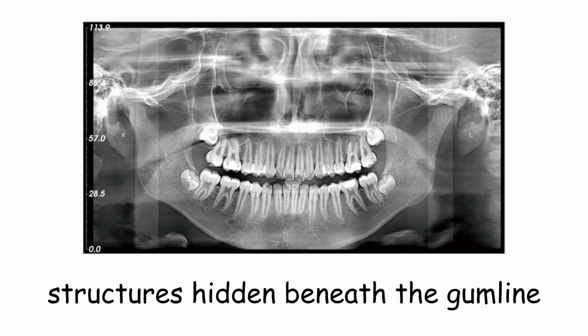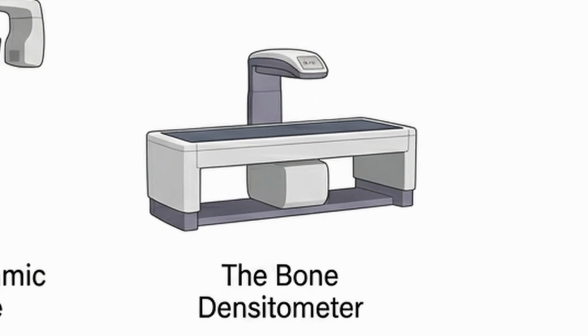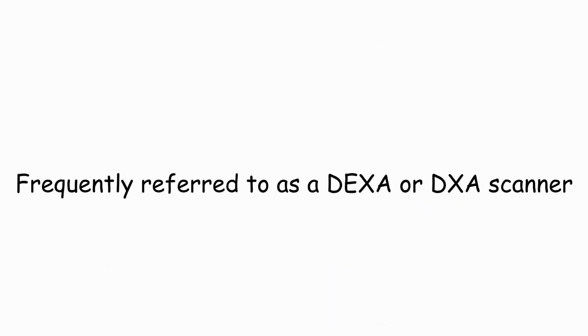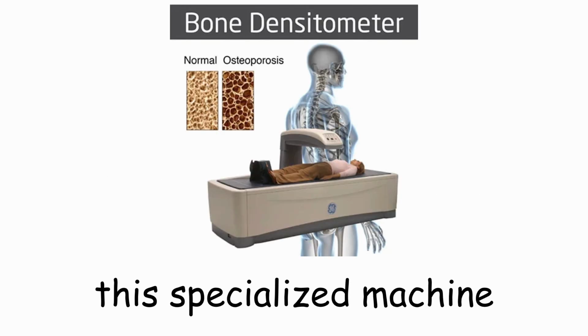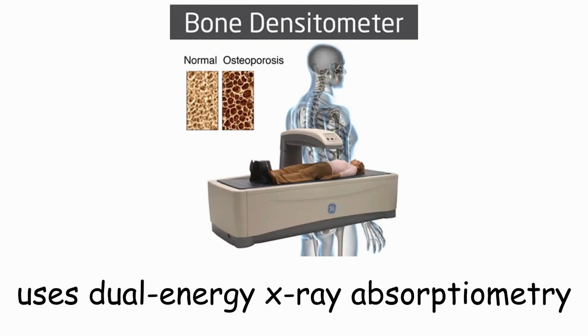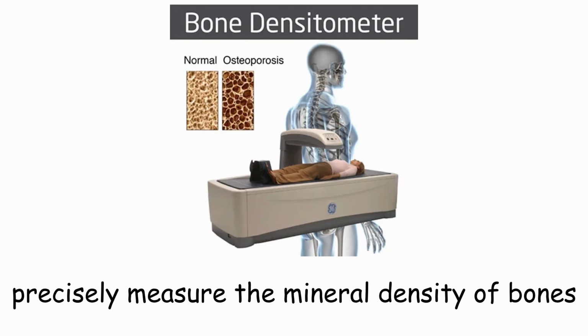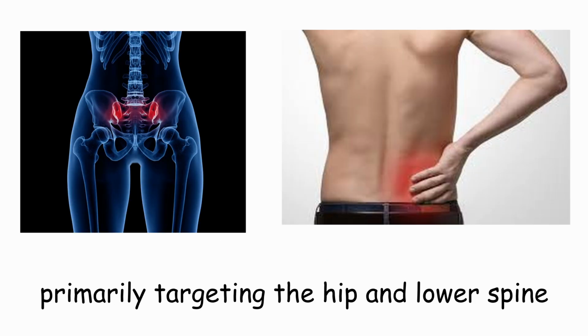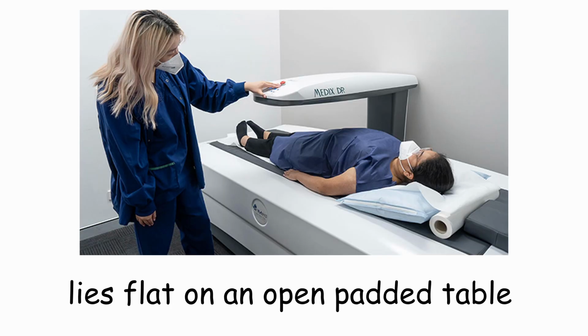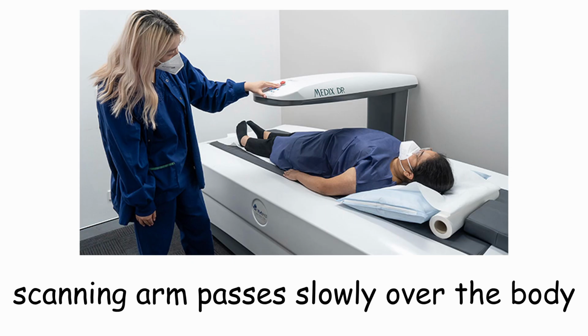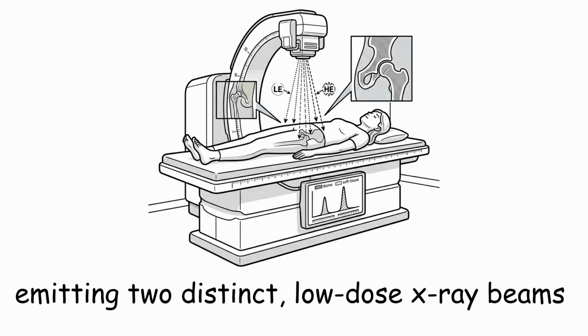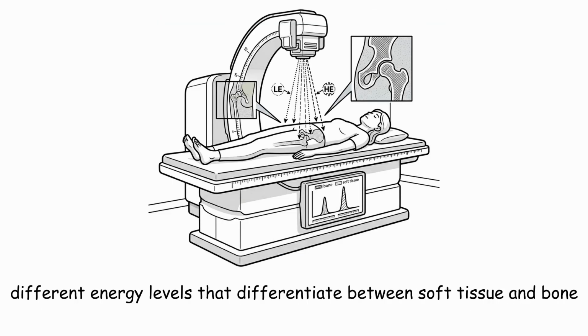The bone densitometer. Frequently referred to as a DEXA or DXA scanner, this specialized machine uses dual-energy X-ray absorptiometry to precisely measure the mineral density of bones, primarily targeting the hip and lower spine. The patient lies flat on an open padded table, while a scanning arm passes slowly over the body, emitting two distinct, low-dose X-ray beams with different energy levels that differentiate between soft tissue and bone.